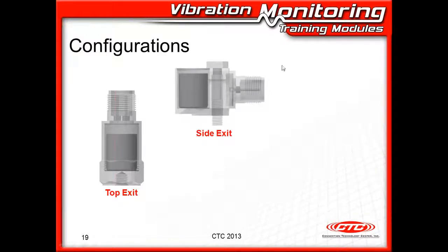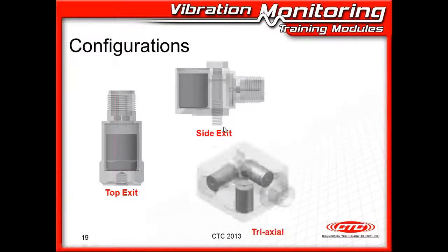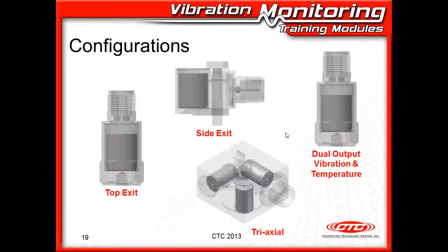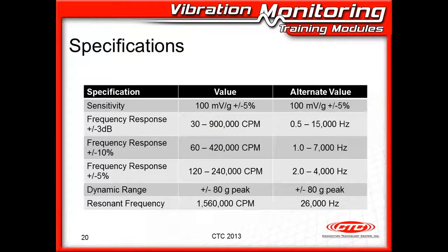Looking at some basic designs, our top exit, our side exit, our triaxial accelerometer. So you can see we've got 3 sensing elements in the same housing here. And of course, the dual output vibration and temperature sensor. So these are just 4 of the basic configurations that we could have. And we'll look a little bit on how they work and what the wiring might be.